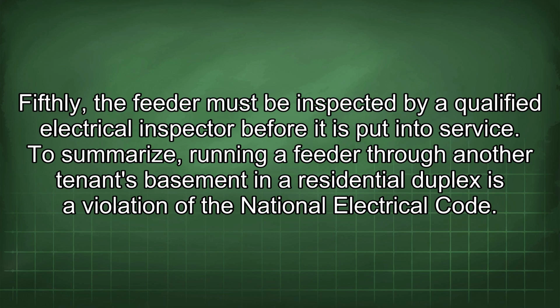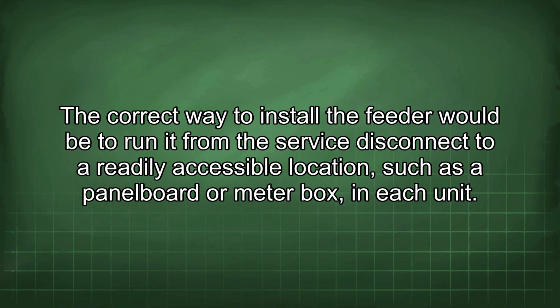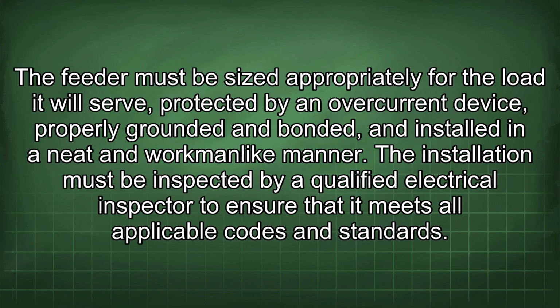To summarize, running a feeder through another tenant's basement in a residential duplex is a violation of the National Electrical Code. The correct way to install the feeder would be to run it from the service disconnect to a readily accessible location, such as a panel board or meter box, in each unit. The feeder must be sized appropriately for the load it will serve, protected by an overcurrent device, properly grounded and bonded, and installed in a neat and workmanlike manner. The installation must be inspected by a qualified electrical inspector to ensure that it meets all applicable codes and standards.